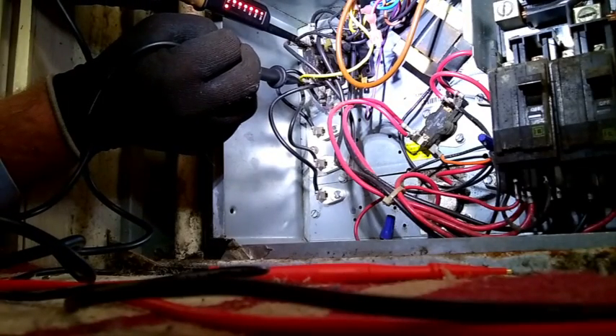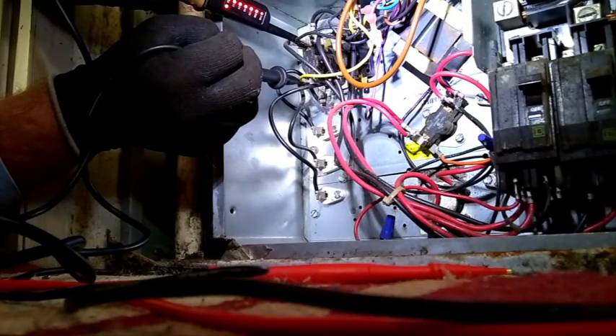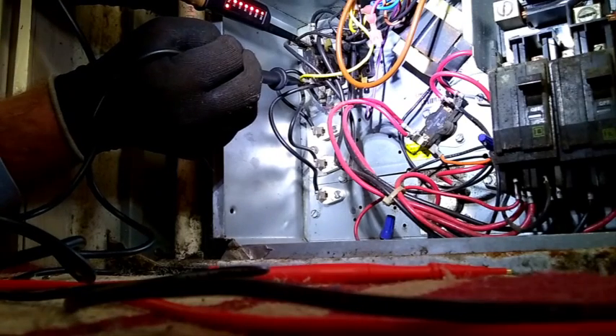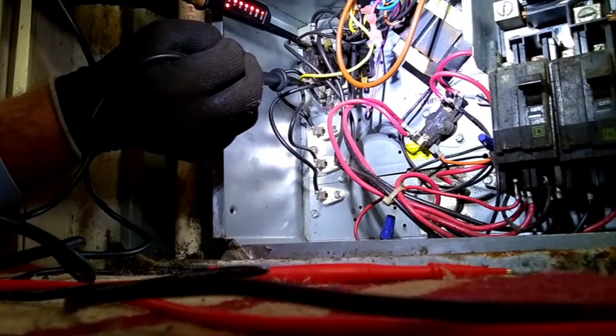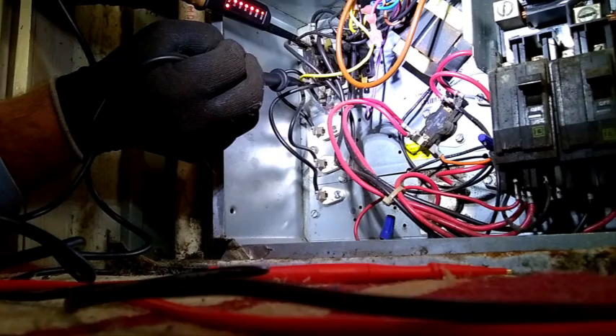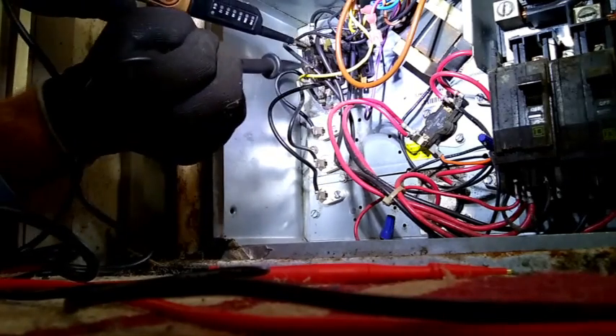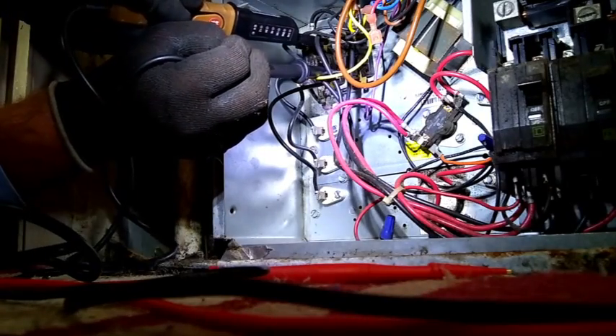You can see there's 240 across the sequencer, meaning it's open right now. I just turned it back on. We have a call for heat from the thermostat. There's no delay because it's an electric furnace, so it should come on in about 10 seconds.